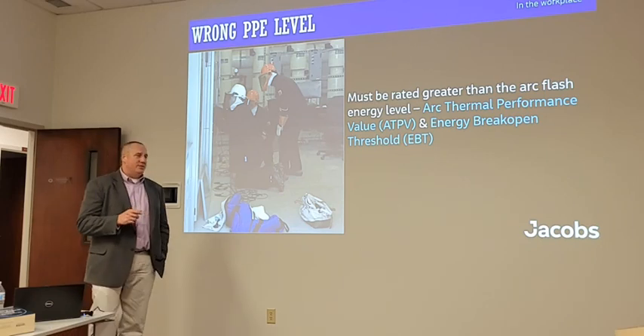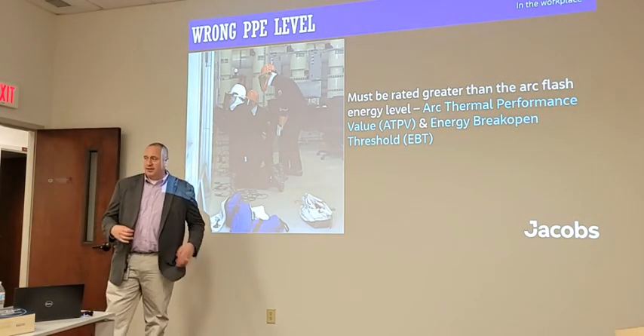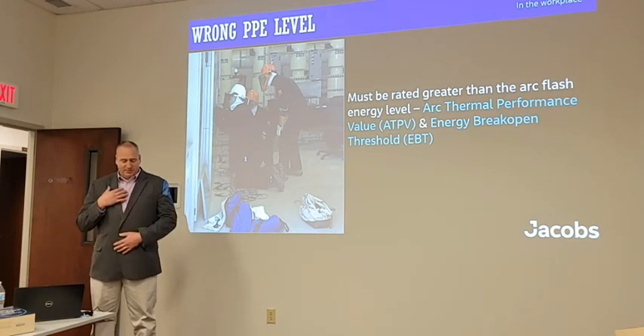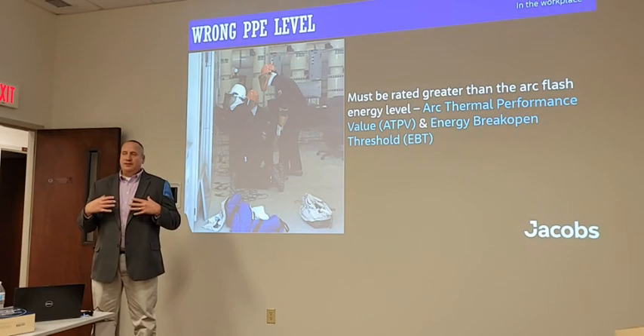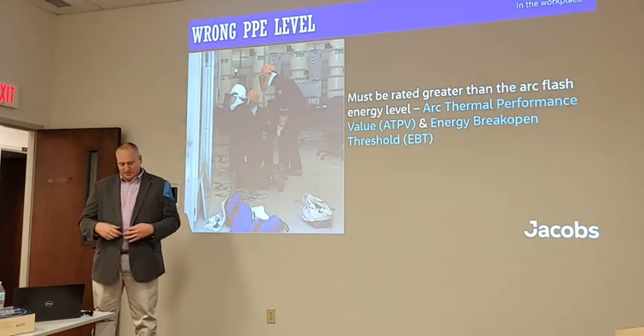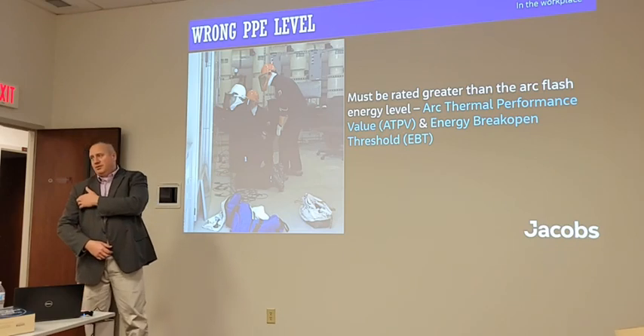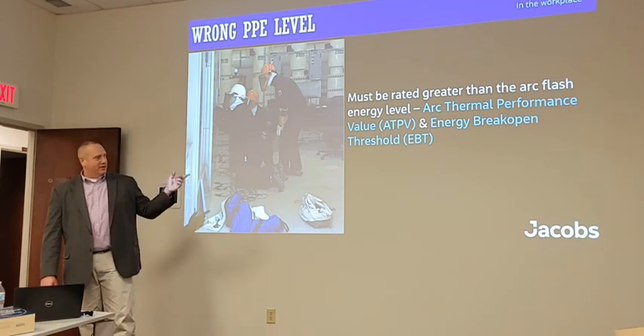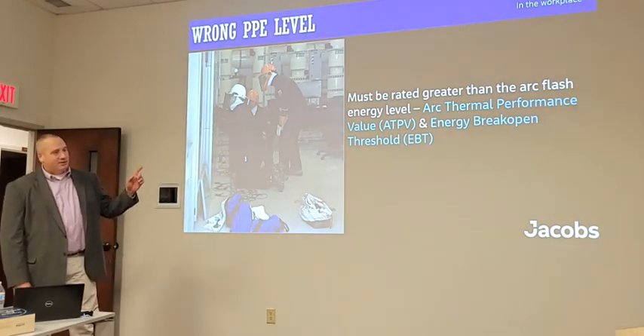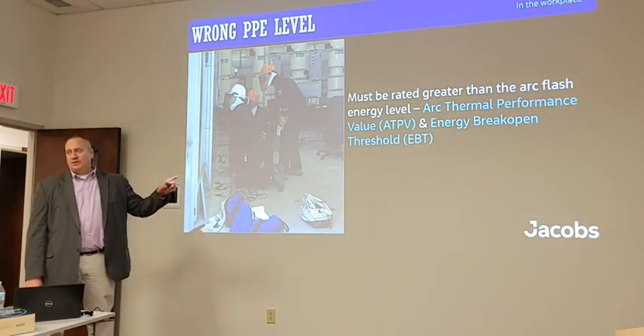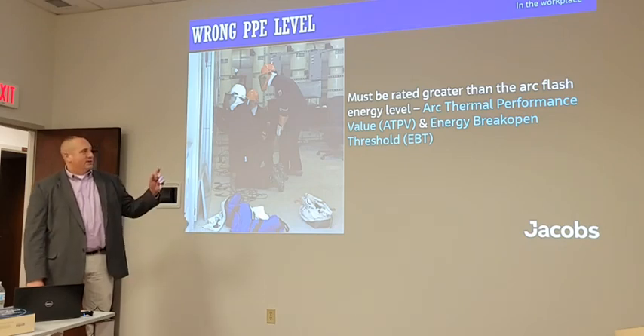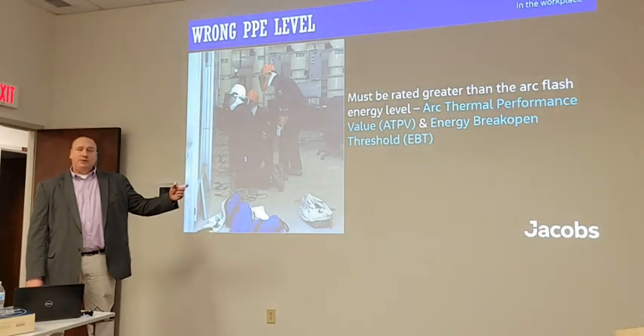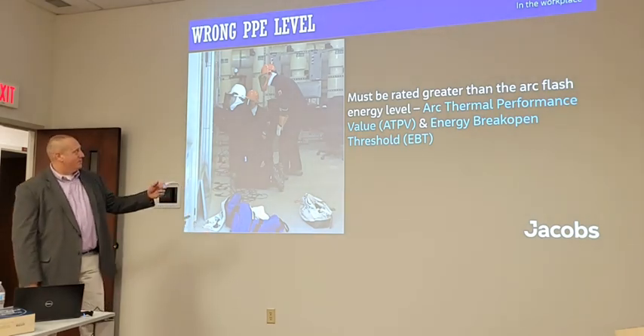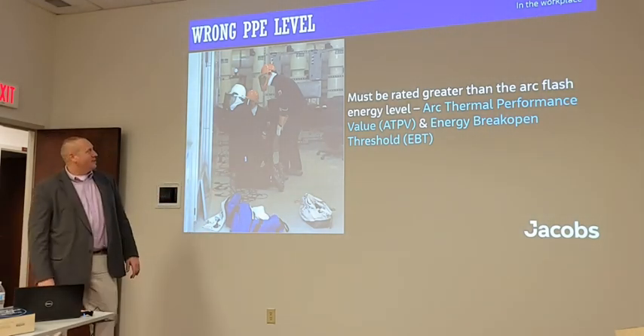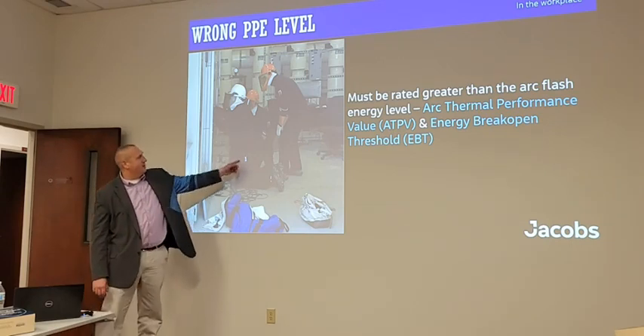The energy break open threshold is when they take the actual garment that's been made and now they put it on a mannequin or put it on something where you button up all the buttons or Velcro, whatever it is, and start exposing it to an arc flash event. And at the moment that a button breaks open or the seam breaks open or something in that garment fails, that's the energy break open threshold. And so they take the lower of these two values, whichever is lower, and that's what they rate that garment for. So whatever that rating is, if it's 12 calories, you don't want to expose it to over 12 calories, which most of our level 2, 8 calorie maximum PPE is. Like this right here is a 12 calorie suit for a category 2 arc flash.